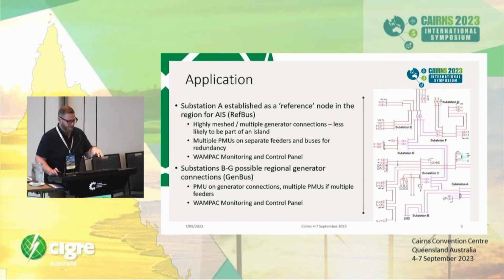And then when you look at the area, for example, if you look at substation E, if we were installing a renewable there, you look at all the various points along the lines where the system could be islanded. The scope of any project you're looking at doing there is going to explode, especially given the way the renewables are working. They're all being installed in similar areas, so you have these zones. So it's not going to be just a one-off. You're going to have to account for the fact that you might have 5, 6, 7 more renewables in that area.